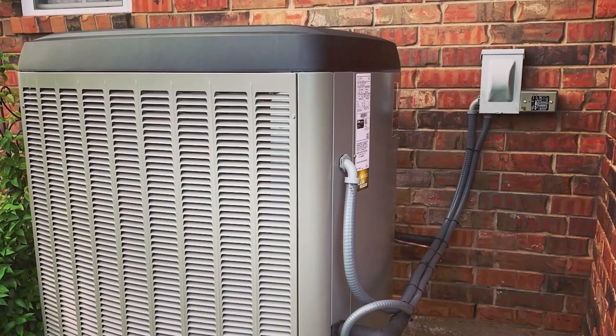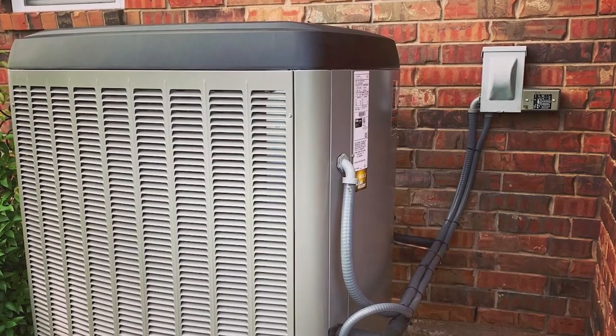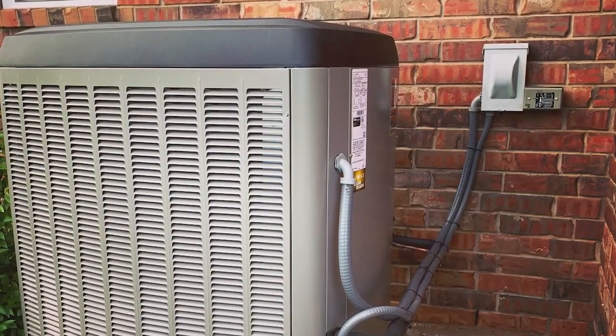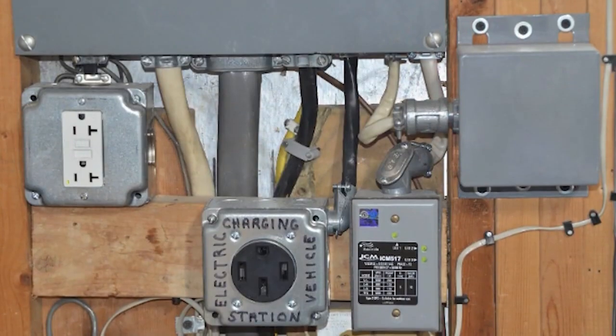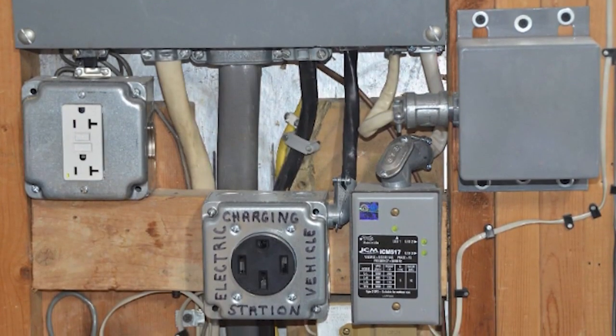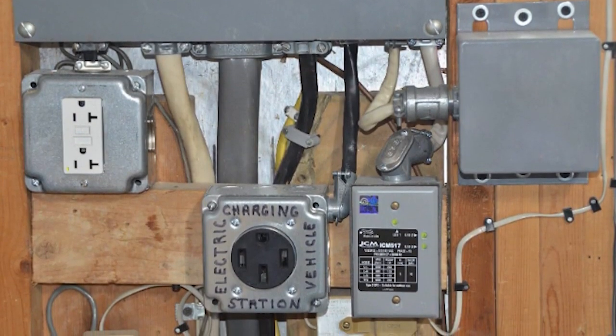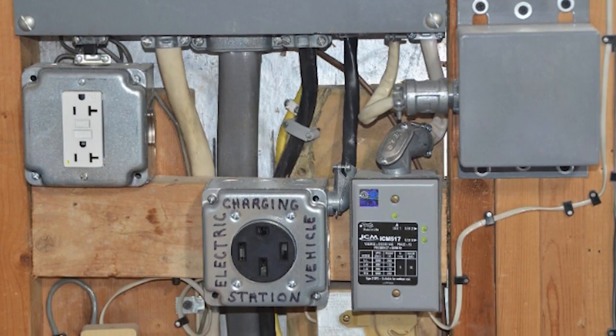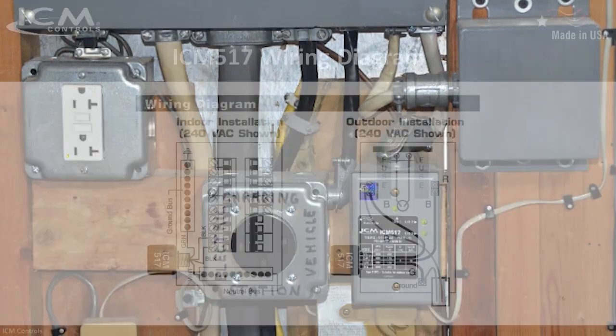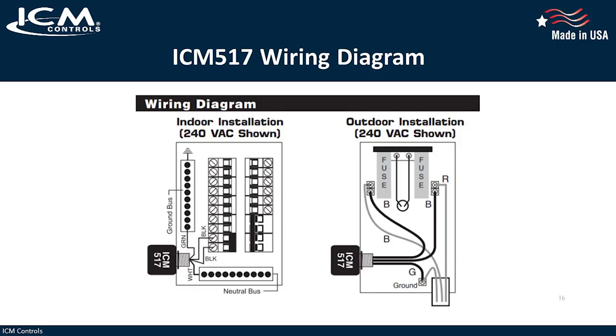Typically, you'll see the ICM 517 installed on the load side of a disconnect. But it can also be installed inside the home with the breaker box. It just has to be installed behind the breaker. In the case of the ICM 517, UL specifies that it has to be behind a 20 to 60 amp breaker. ICM opted to go with a Type 2 device, and not a Type 1 whole house device.